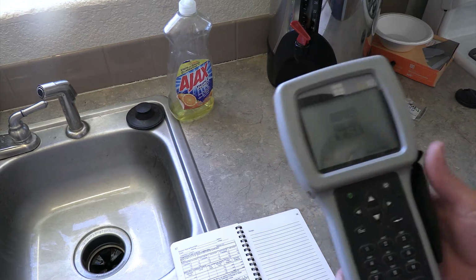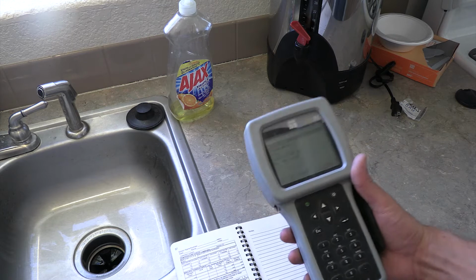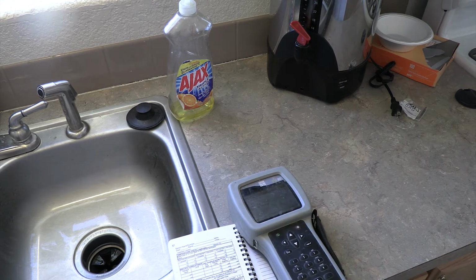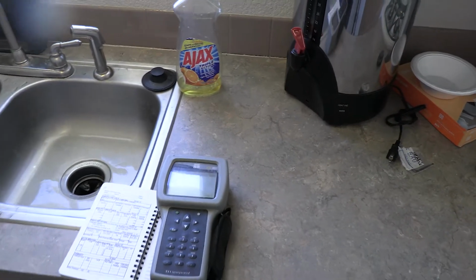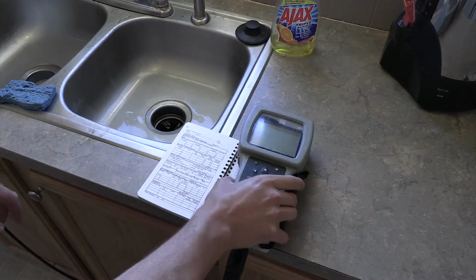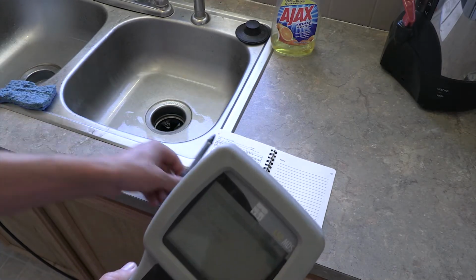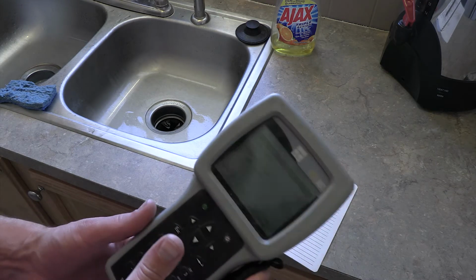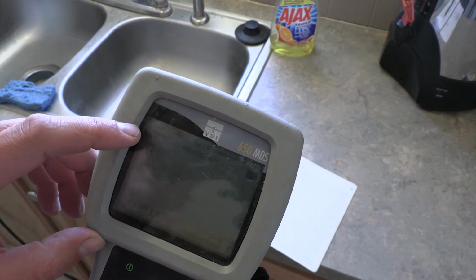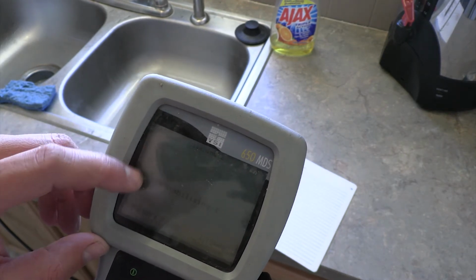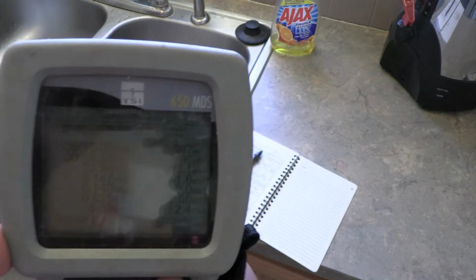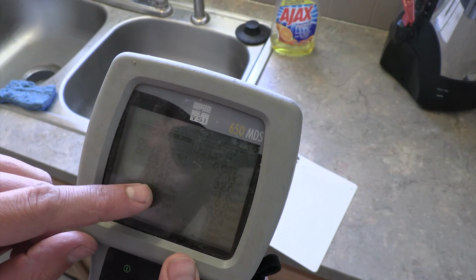All right, so let's go over here to the data logger and look at that for the first time. Let's see what we got here. The data logger is kind of annoying, but it does a good job. It's pretty simple when it comes to calibration. Okay, so we got our calibration book, blank book, and we have our data logger. The first thing we're going to do is run it on tap water, and then we'll let it sit for a minute or two, and then get our initial tap water reading. Then we'll do the same thing at the end and see how much it's changed. So we got our ports in. While it's reading, let's go ahead and set up our book here.